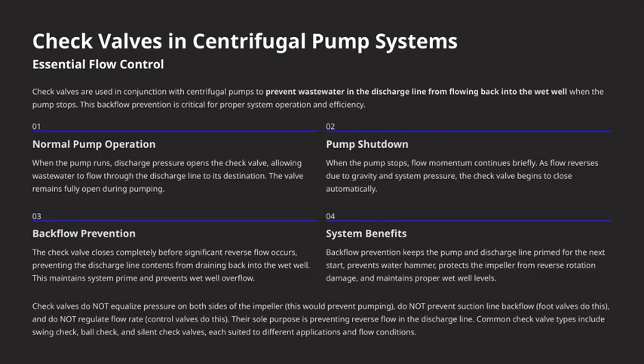It's important to remember what check valves do not do. They do not equalize pressure on both sides of the impeller. That's not their role and would actually prevent pumping. They also don't prevent backflow in the suction line. That's the job of foot valves. And they don't regulate flow rate. That's the function of control valves. Their only purpose is to prevent reverse flow in the discharge line.